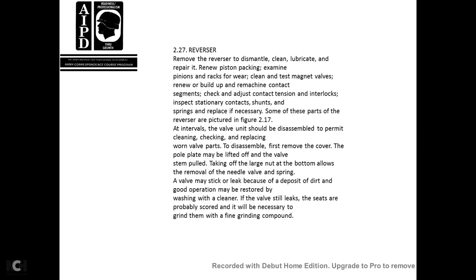227, the reverser. Remove the reverser to dismantle, clean, lubricate and repair, and renew the piston packing, examining the pinions and rack for wear, cleaning, testing magnetic valves, renewing and rebuilding and remachining contact segments, checking and adjusting contact tensions, interlocks, inspecting stationary contact shunts, and replacing springs if necessary. Some of these parts of the reversers are pictured in figure 217.